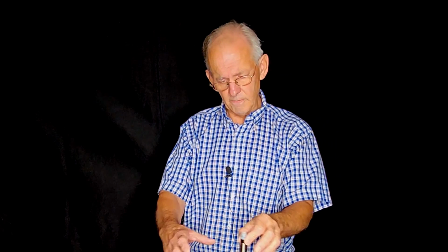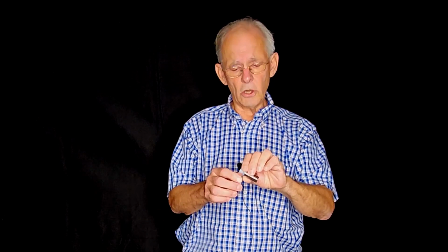And it's pretty broad. You can't pick up a small target with it. It's an area type sensor. If there are different heights, it's going to kind of average the height of the thing. But it's quite good at sensing pile height and that kind of thing, or tank levels. So that's an ultrasonic. And again, it puts out the same kind of signal that the PLC sees, which in this case is 4 to 20 milliamps.